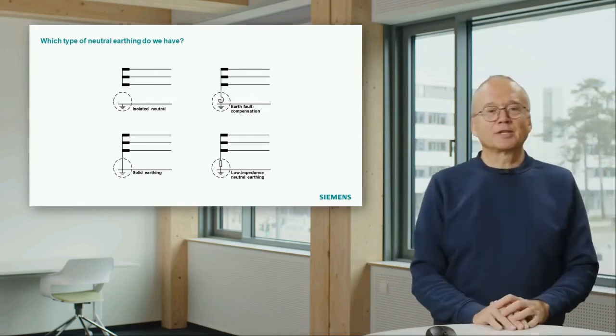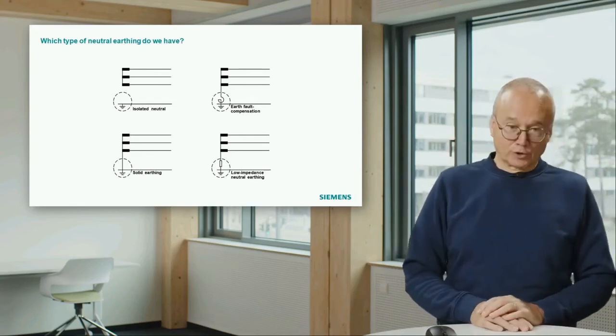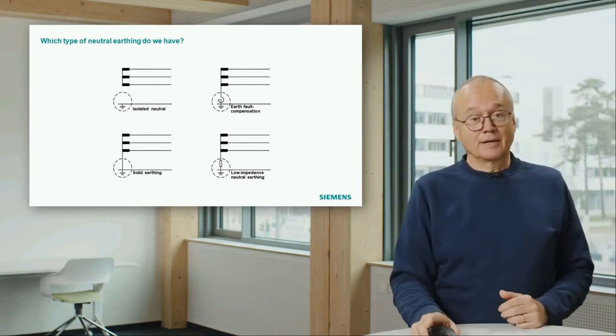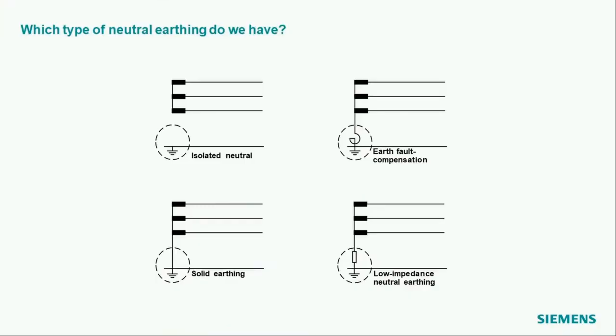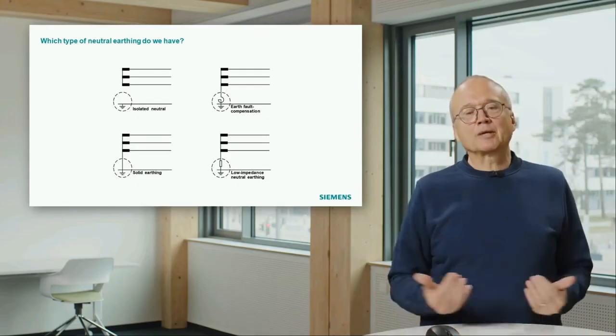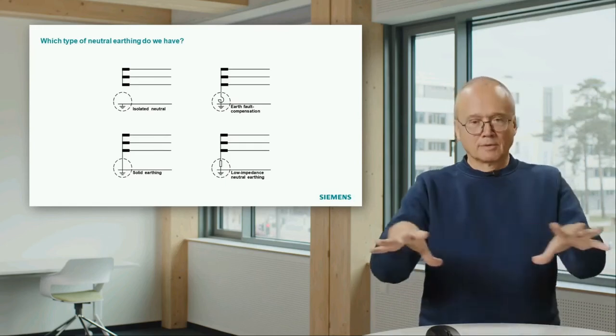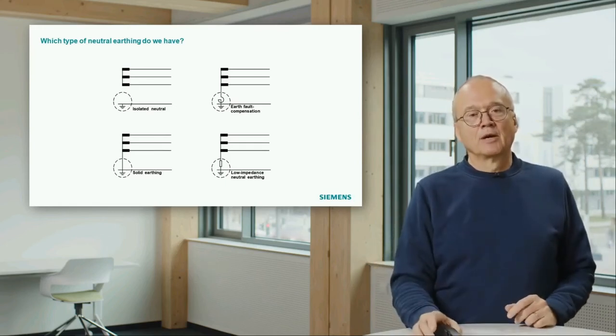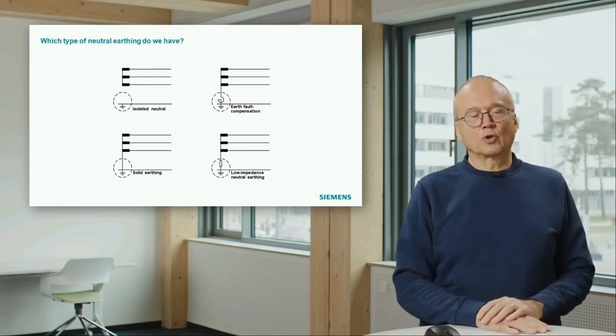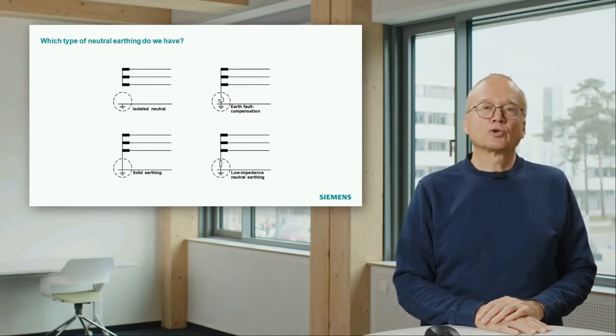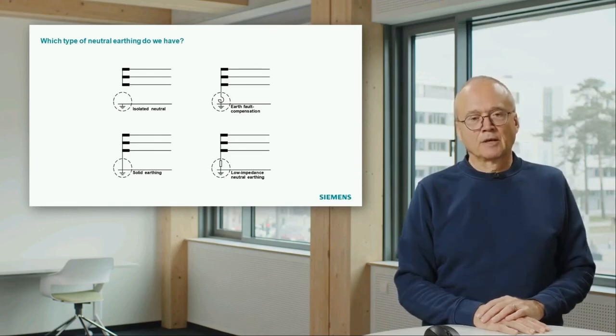The next point we have to consider is the neutral earthing. And that is a point which has a really big impact on protection. What we see here is one side of a transformer in the system, and this transformer has a star point. Now the big question is, what do we do with the several star points in the system? One thing you can do is so-called solid earthing. That means you connect the star points to ground. And that is what you typically do in transmission systems. There normally the star points are grounded.